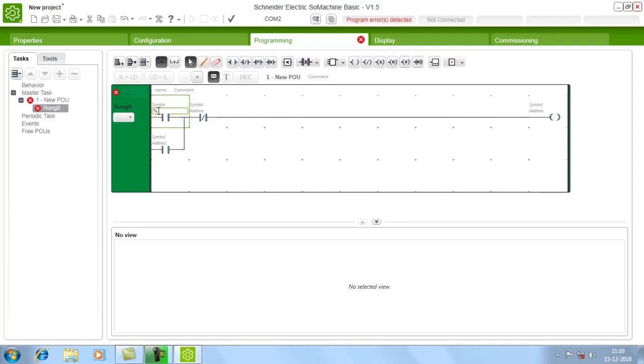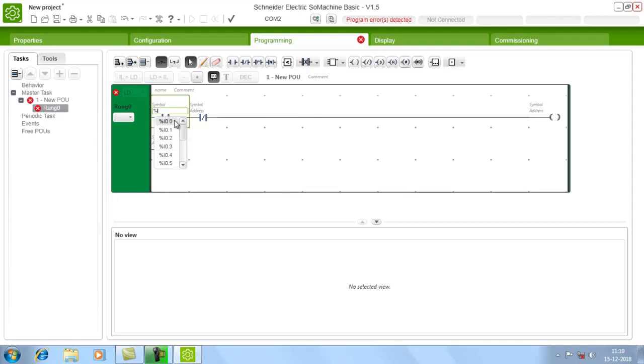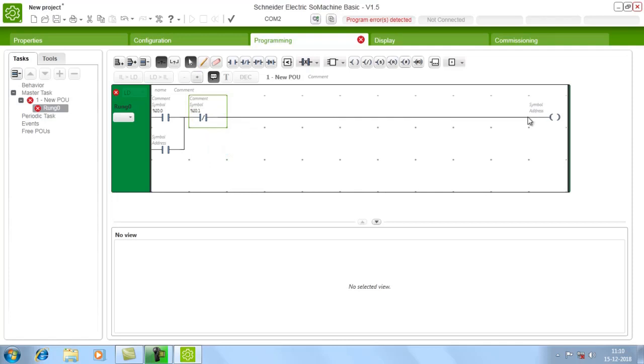Once you click Address, a percentage symbol will be displayed. For inputs it starts with %I — once you type I, all the inputs will be listed. As mentioned, the PLC has 14 digital inputs, from %I0.0 to %I0.13. Choose whichever input you want; I am choosing I0.0. For outputs, the address starts with Q — there are 10 digital outputs from Q0.0 to Q0.9, so just give Q0.0.